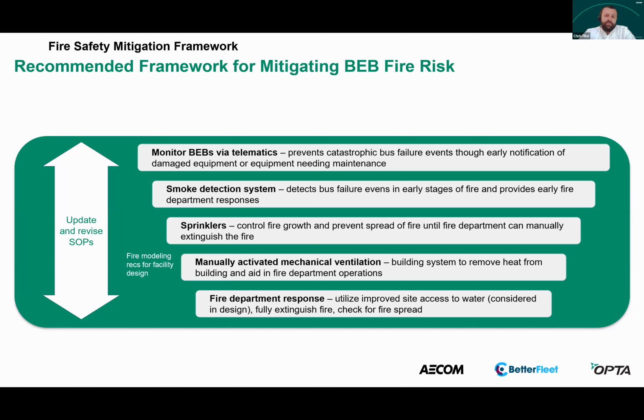If battery management systems fail to stop the thermal runaway event, building protection systems are our next layer of protection. Options include smoke detection for early fire department response and occupant evacuation, suppression capable of preventing fire spread from asset to asset and impacting the building structure, and manual smoke and heat removal systems to aid fire department response. One note on ventilation: it's important to ensure ventilation systems don't activate too early in a fire event, which may delay sprinkler head activation and cause the fire to grow.